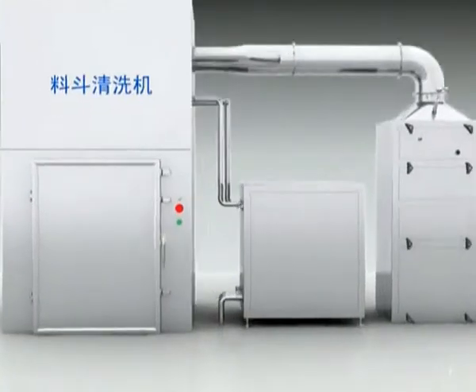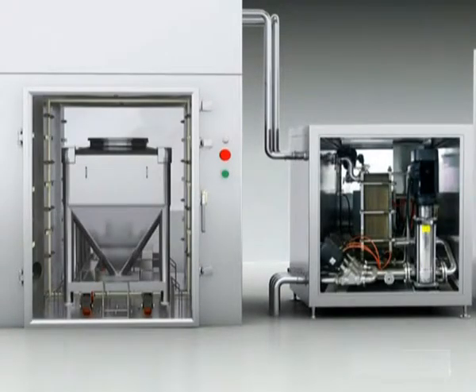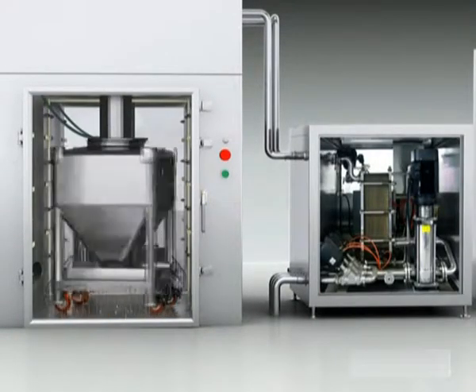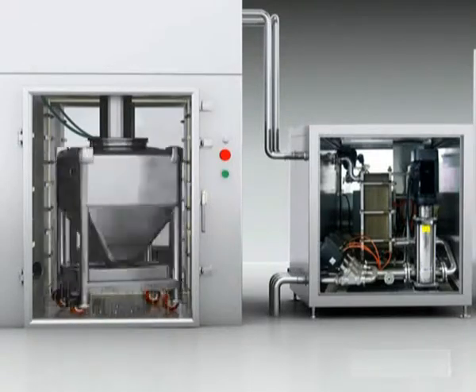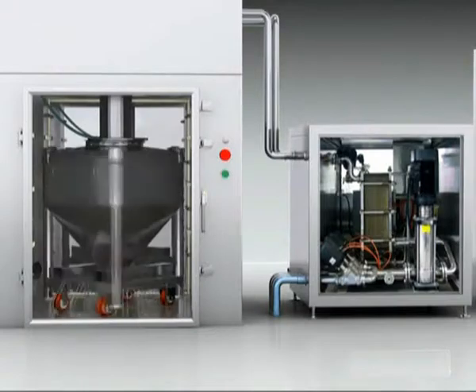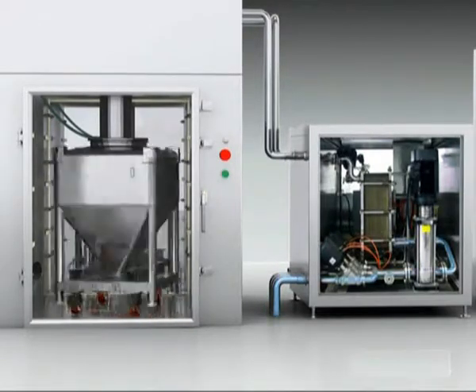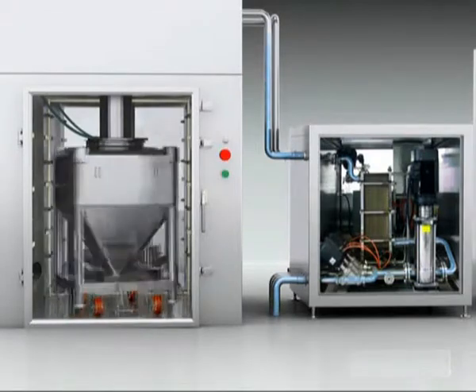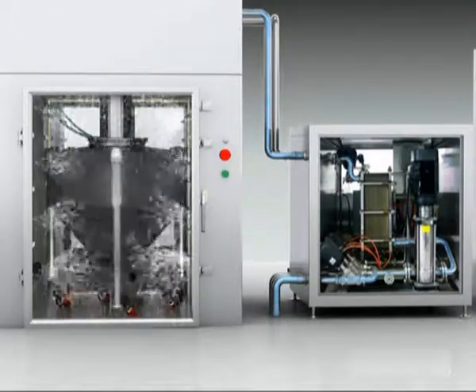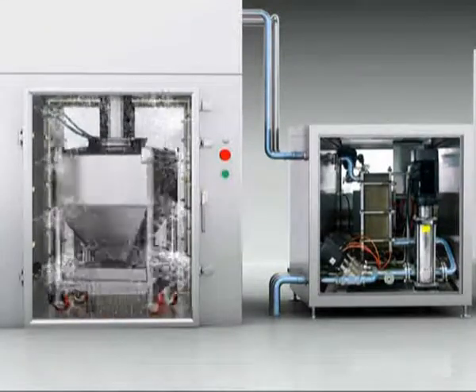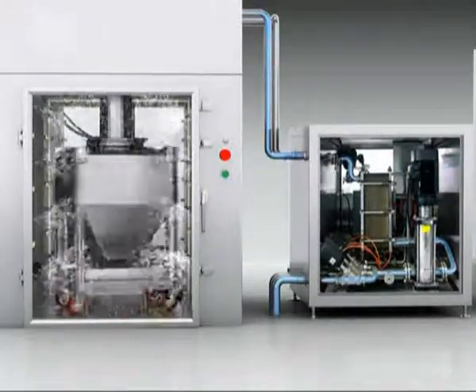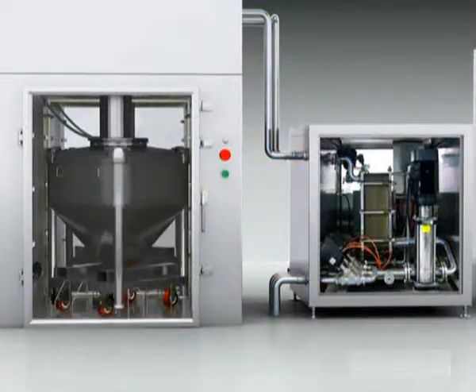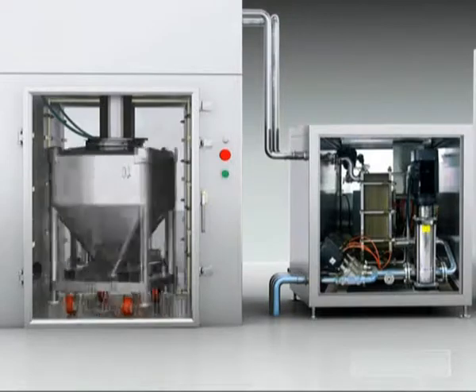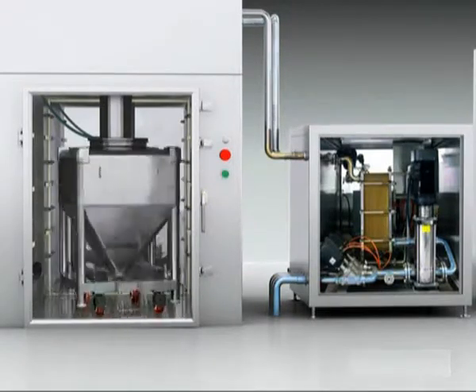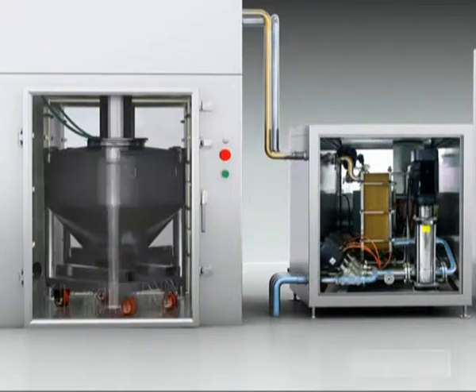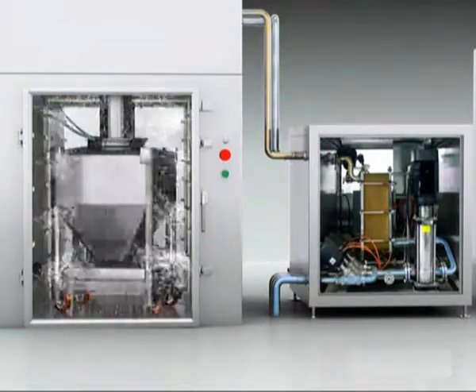Pre-washing applies tap water. Tap water pressure is raised by the boost pump inside the pump station, and flows through the piping to the top washing board and the nozzles on the washing chamber walls for internal and external surfaces cleaning. Followed with tap water pre-washing, hot water washing cycle runs automatically. In this stage, the heat exchanger inside of the pump station works and the hot water pressure is raised by the boost pump inside the pump station and flows through the piping to the top washing board and the nozzles on the washing chamber walls for internal and external surfaces cleaning.